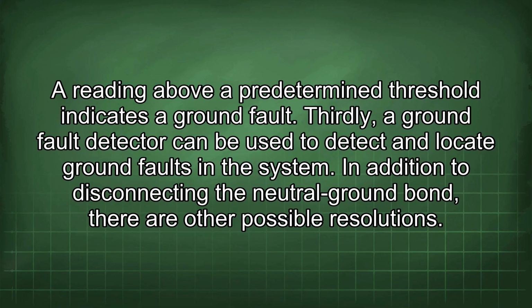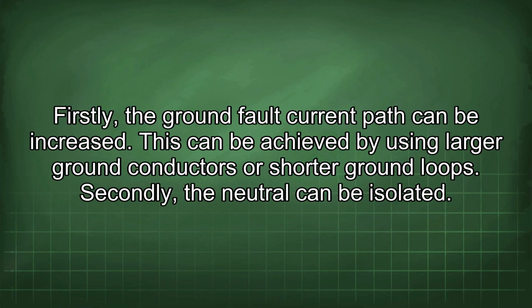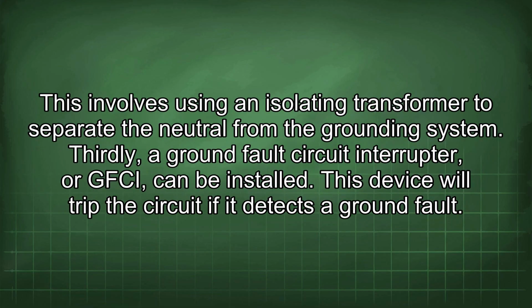In addition to disconnecting the neutral ground bond, there are other possible resolutions. Firstly, the ground fault current path can be increased. This can be achieved by using larger ground conductors or shorter ground loops. Secondly, the neutral can be isolated. This involves using an isolating transformer to separate the neutral from the grounding system. Thirdly, a ground fault circuit interrupter, or GFCI, can be installed. This device will trip the circuit if it detects a ground fault.